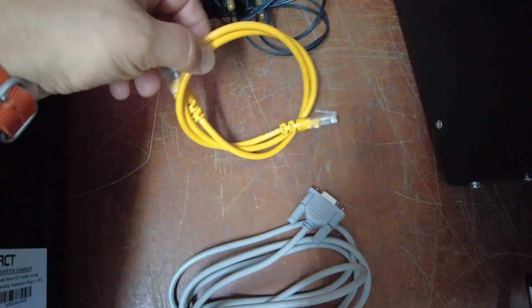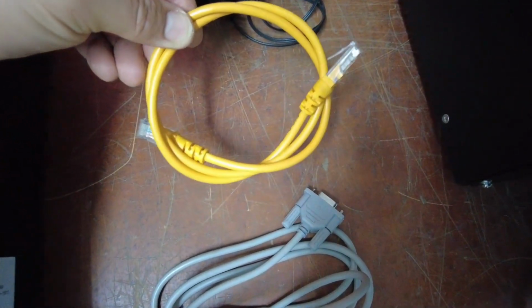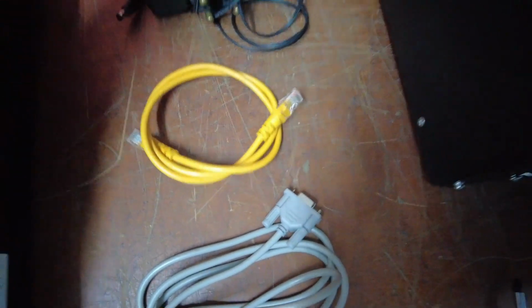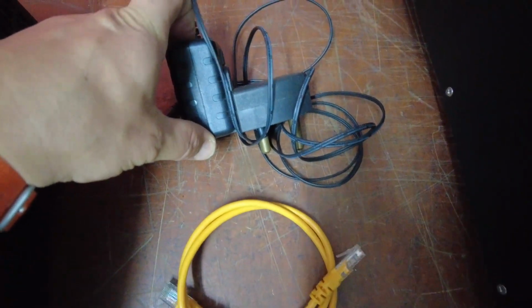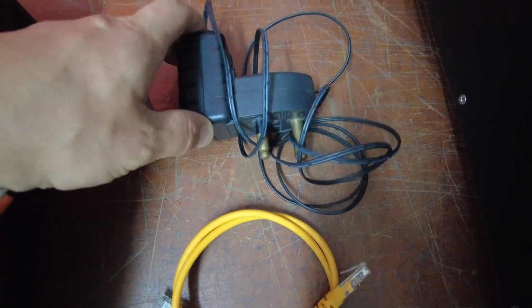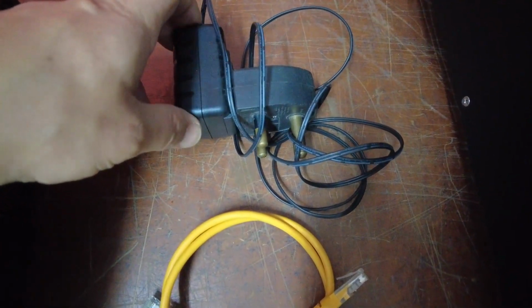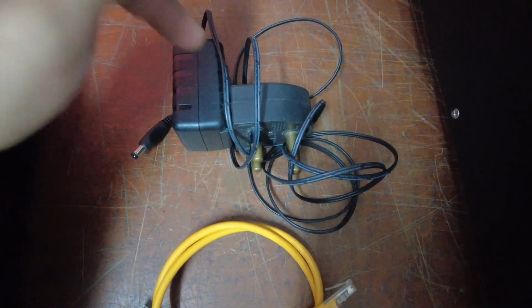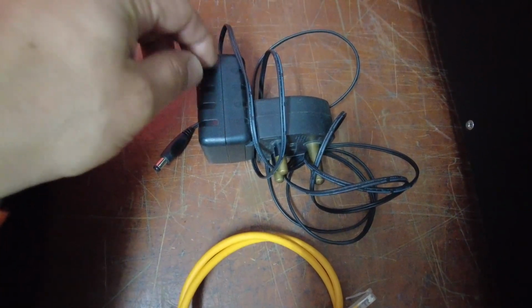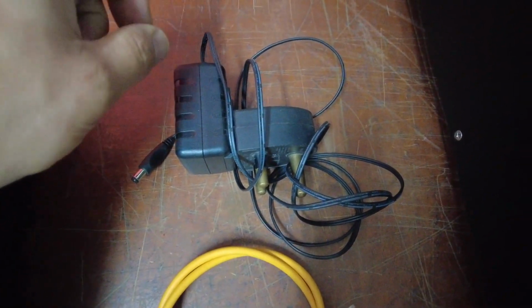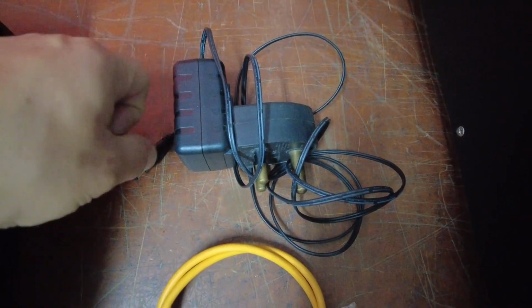You do need the specific cable that was supplied with the inverter, as the pinouts on this RJ45 are different. Then you will need a standard networking cable, pin to pin, as well as a DC 12 volt power supply at approximately 1 to 1.5 amps. Unfortunately, you do not get this power supply with the BMS box, so you need to purchase it separately.